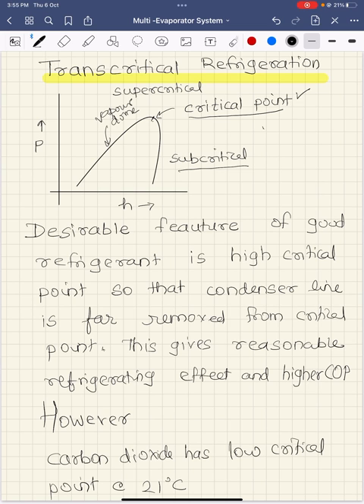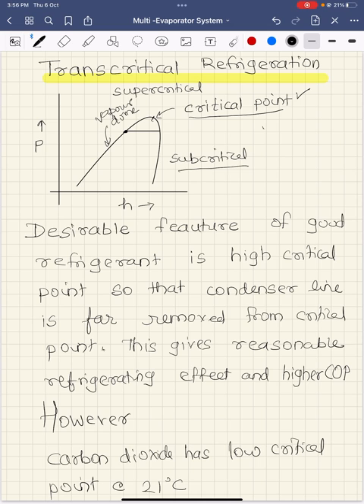For example, the refrigerant is saturated liquid over here. As it is heated, the refrigerant boils and it becomes dry saturated gas. But beyond this critical point, what happens is these two distinct regions — that is liquid and gas — disappear, and what is left is a supercritical region. If it is clear that below the critical point is the subcritical region where the phenomena of boiling or evaporation is distinct, and above the critical point there is no boiling phenomena, then the transcritical refrigeration cycle will be clear to us.